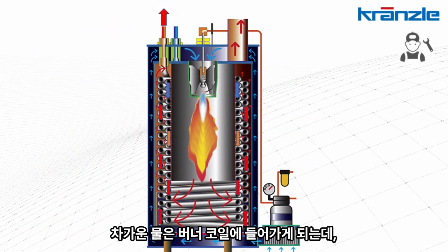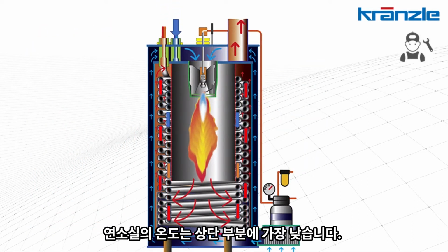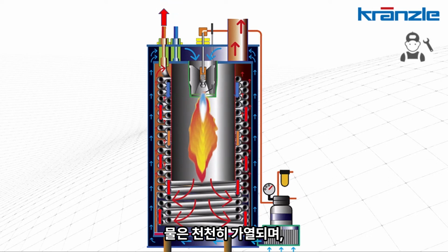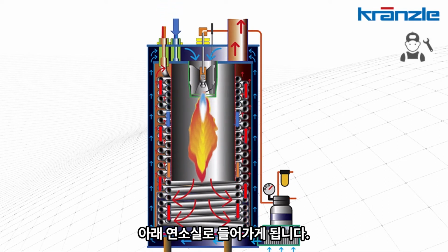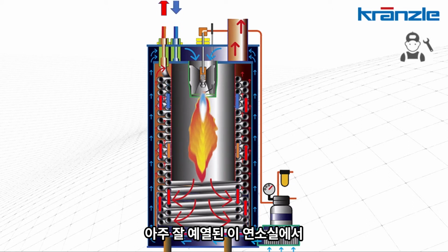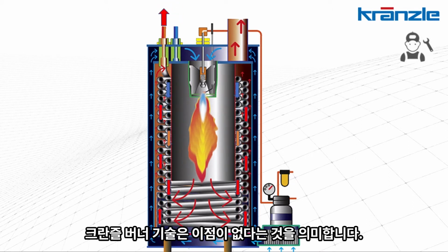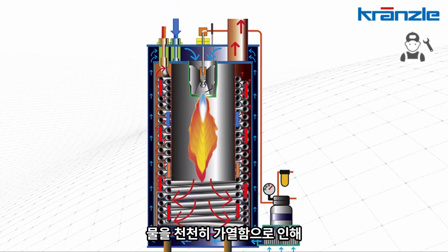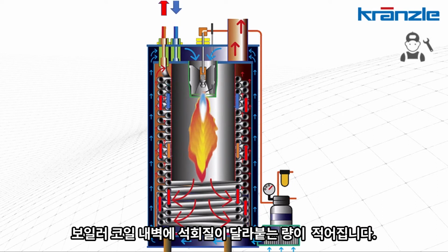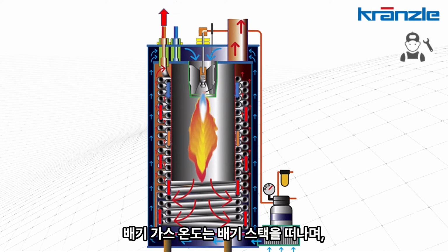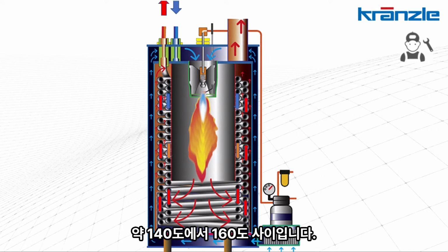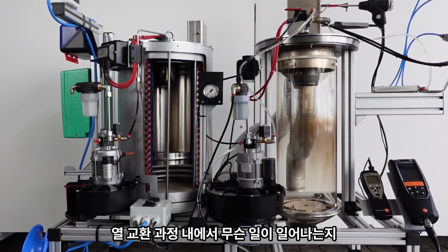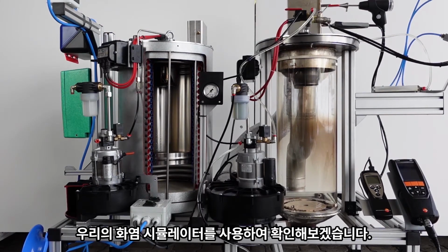The cold water enters the heating coil in the inner coil. The temperature in the heating chamber is lowest in the upper section. The water heats up only slowly and enters the lower combustion chamber well preheated, where it is fed into the outer coil. The Kraenzle burner technology means that there is no dew point, and due to the slow heating of the water, there is only a small amount of calcification. The exhaust gas leaves the exhaust stack after the heat exchange process with a temperature of only approximately 140 to 160 degrees Celsius. What happens inside the heat exchanger we will now see using our flame simulator.